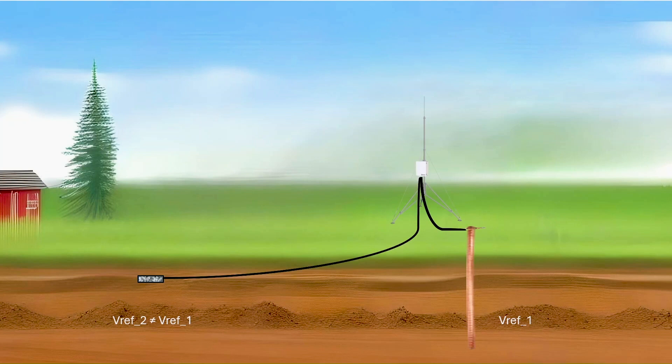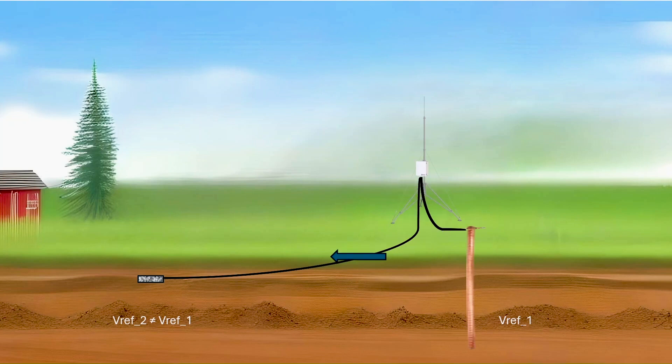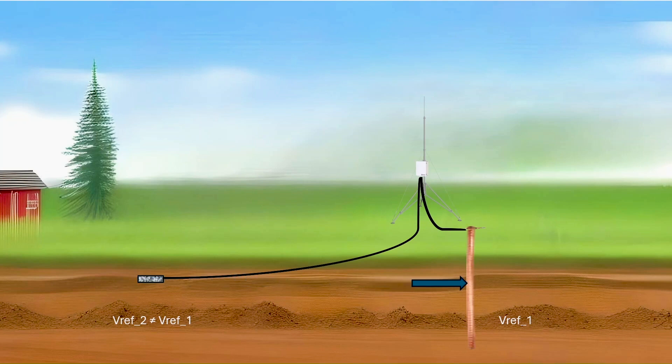The data logger sends current to the sensor through an excitation channel which returns through a ground wire, but the soil and water provide an alternate path for the excitation to return to the data logger. This ground loop forms a galvanic cell with the soil water acting as the electrolyte.